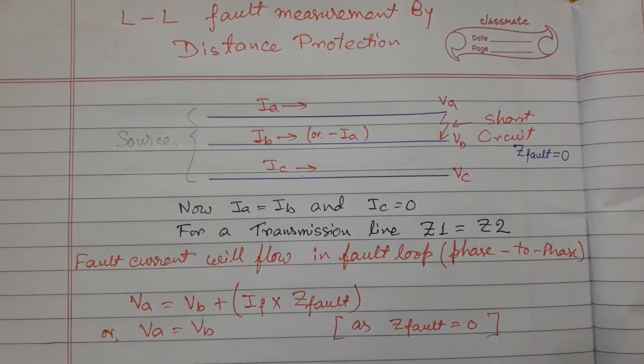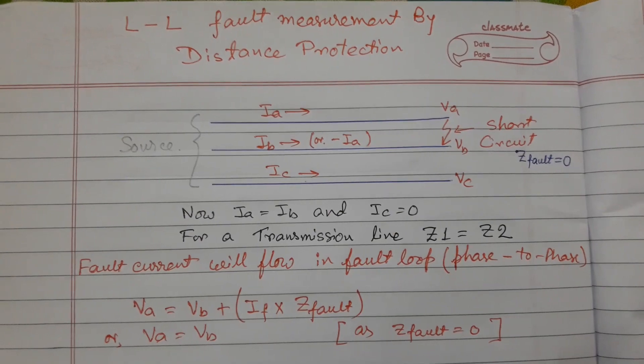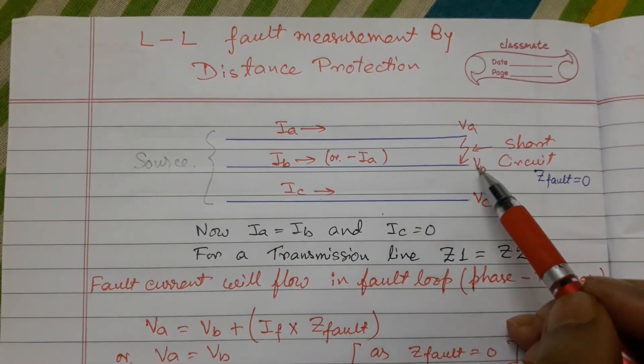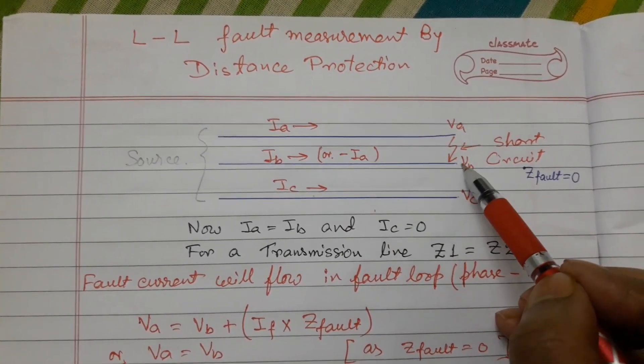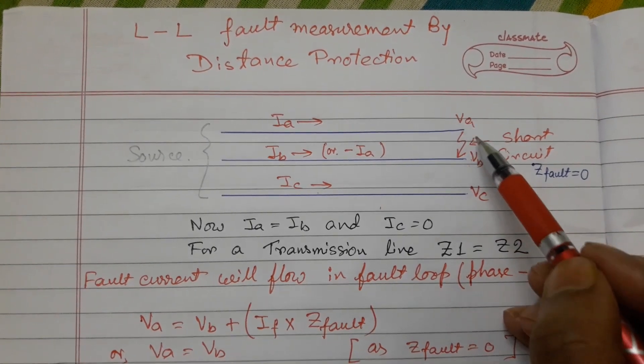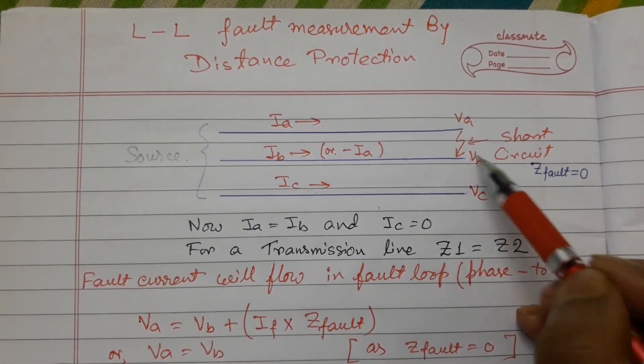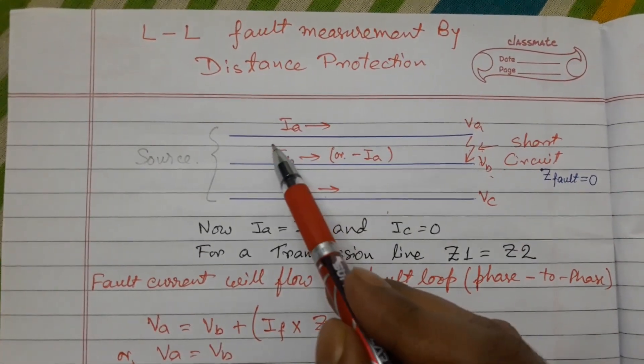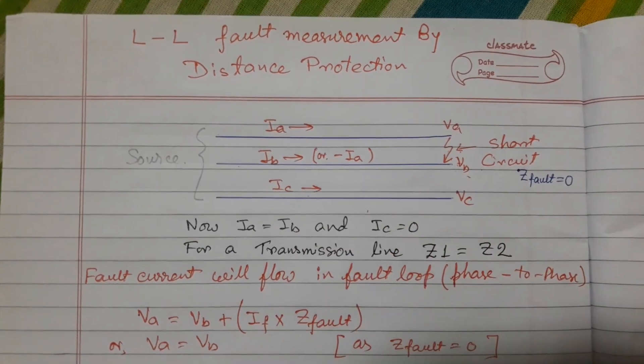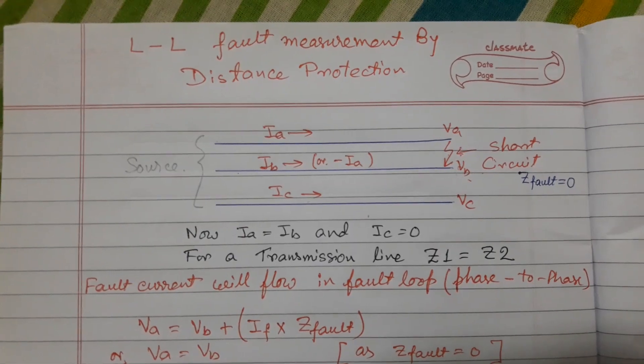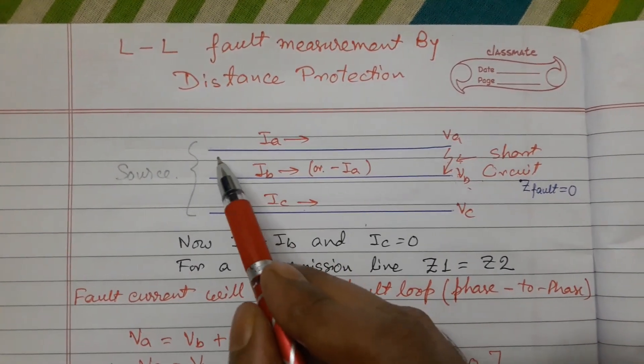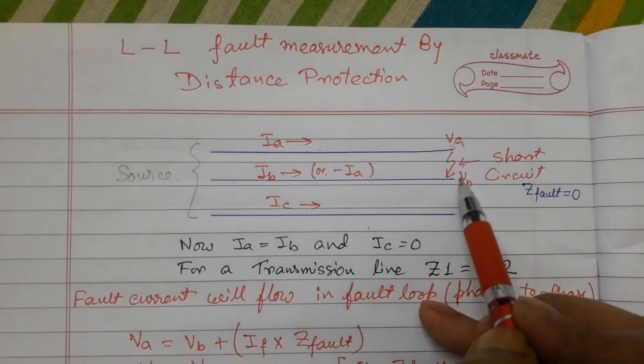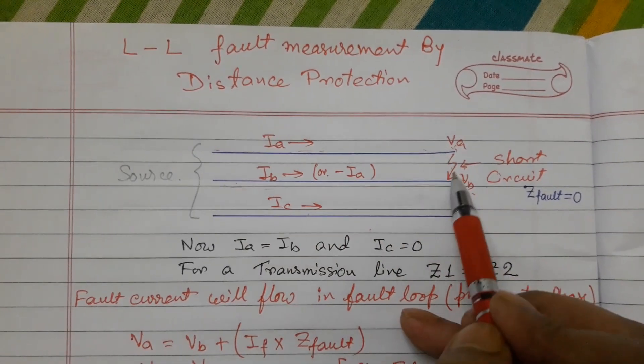In this video we will discuss line-to-line fault impedance measurement by a distance relay. This is a three-phase transmission line and suppose a line-to-line or double-L fault appears between phase A and phase B, with the impedance of fault equal to zero. This is the fault loop — the path in which the fault current traverses. Since the fault appears between these two phases, the fault current will follow this path.